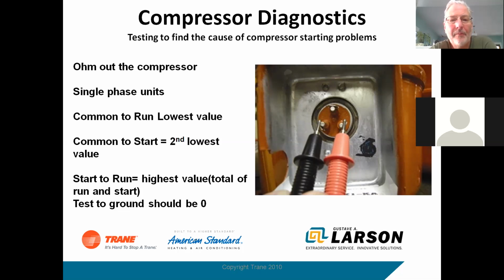Single phase units, we want to check common to run, common to start, and then of course start to run, to see that all the windings are in good condition. And then we also want to go to ground to make sure we don't have a ground on any of the windings.